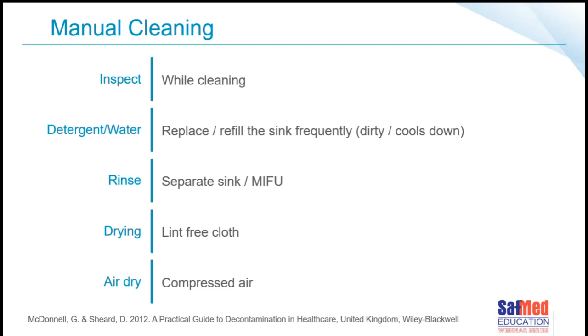And of course, over time, the water is going to cool down, which then renders the detergent a little less effective. I need to rinse in a separate sink, again following the manufacturer's instructions for use. We saw in the Thomson Retractor, at points it said under running water, other times it said under soak in the water. You need to follow those instructions. Drying with a lint-free cloth or with compressed air, depending on the requirements of the instructions for use.